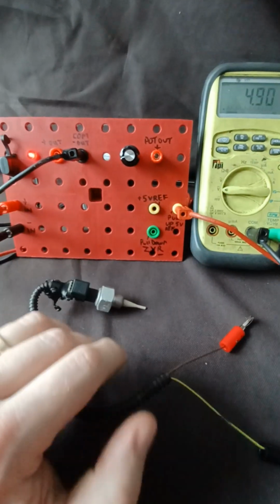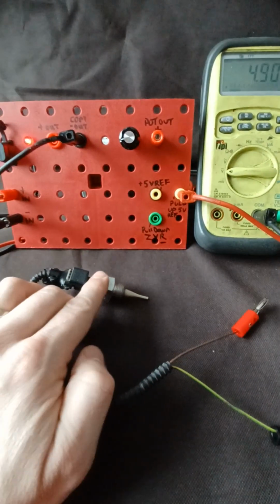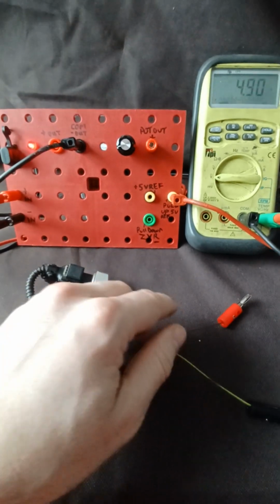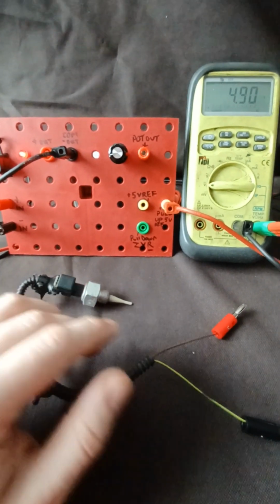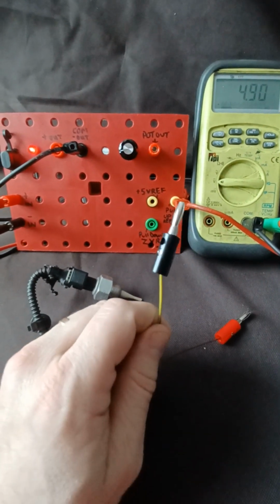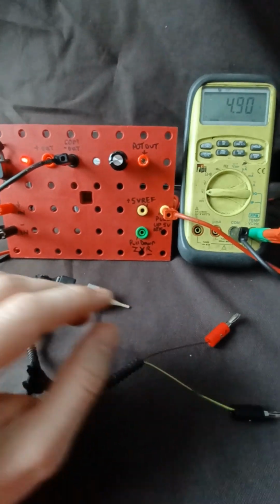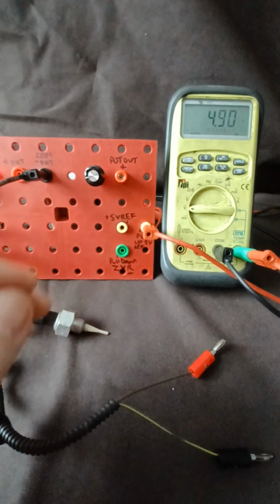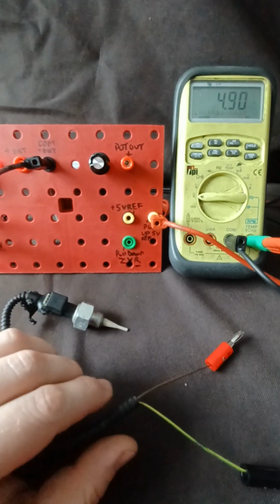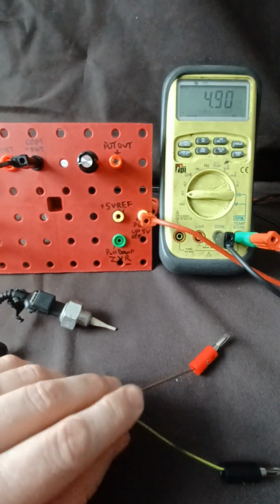All right, so if we see high voltage there, that means we have an open. That could be a damaged sensor. It could be a fault on the ground side. It could be a fault on the 5-volt reference supply side. So a number of things, but a high voltage fault, a -3 fault, is what we would get for that, for an open circuit.